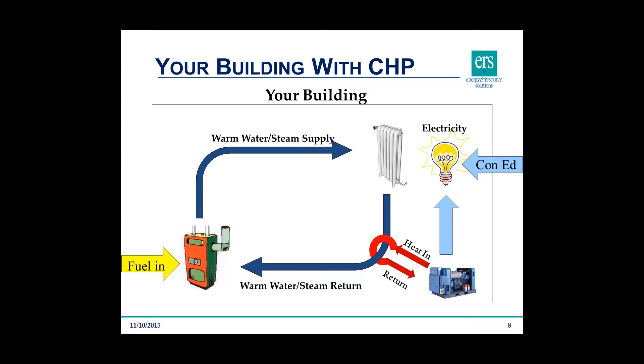Buildings have a lot of options in terms of how they set up their CHP installation and exactly how they use their heat output. This is an example of one building incented by NYSERDA. Here we've got a natural gas supply running two 75 kilowatt combined heat and power systems. The electrical load provides 24/7 power, and during an extended grid outage it would also power critical systems in the facility. The heat output runs into a hot water loop for domestic hot water, space heating, and laundry. This is just one example of how a system decided to set up their CHP.